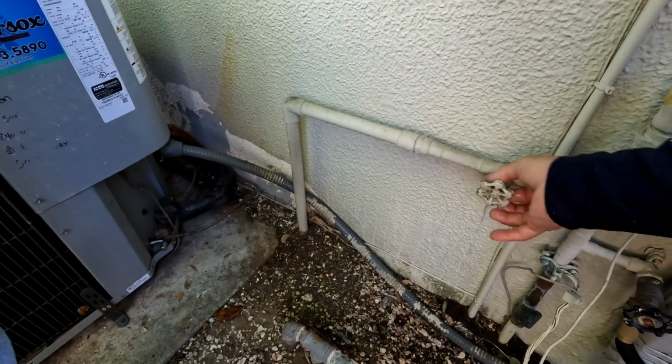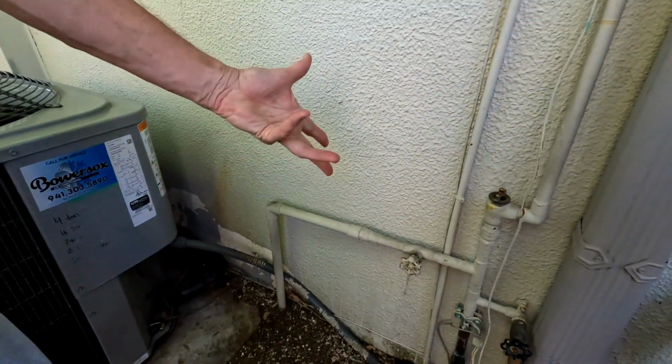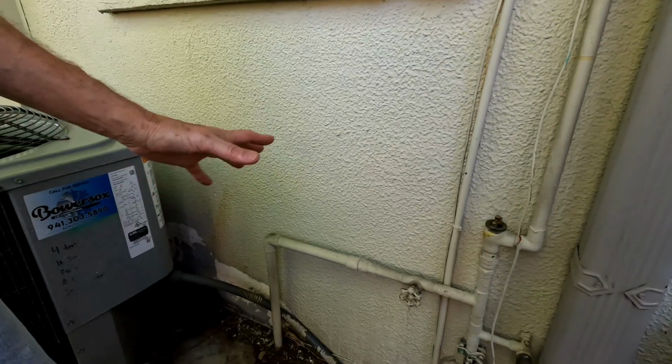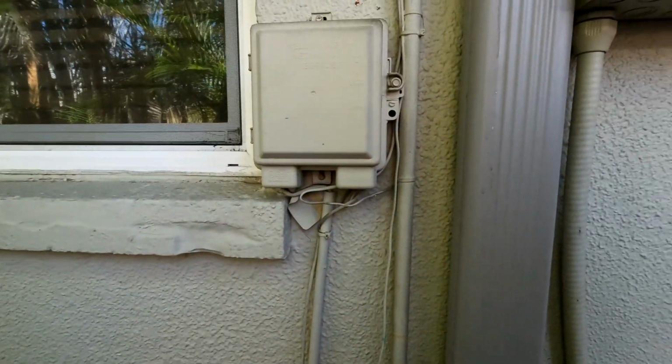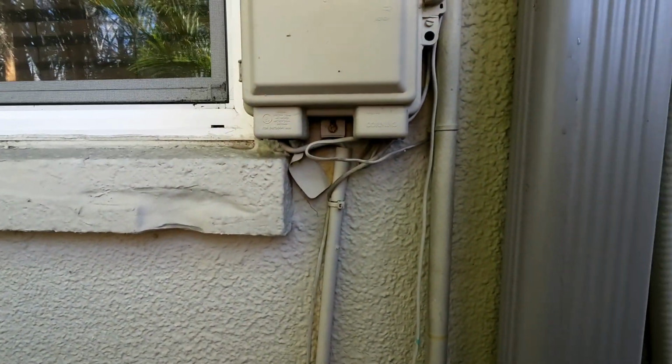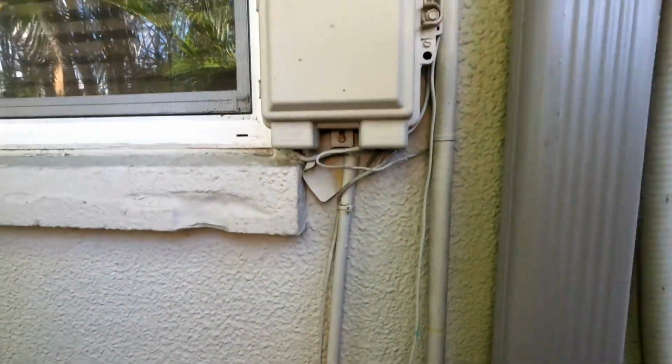Okay. Did you try to tighten this packing nut? Not because of all that crap there. I did not touch it. I just said, he's coming anyway. I'll let him do it. Because it may have to be replaced. I don't know. No, you just need to. We'll just tighten it up. We'll try, anyways. Yeah, we need to repack it or replace it.